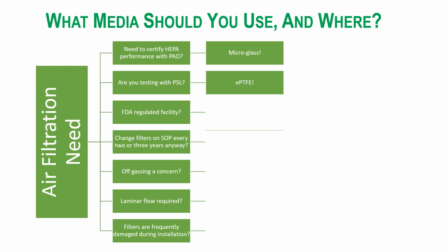You can't just switch from PAO to PSL. You have to buy a different particle counter. You have to buy a different nozzle. It's a completely different monster to adopt. So if you're an FDA regulated or Health Canada regulated facility, you probably want to stay on what you're using already, or you want to be ready to explain why you switch to a PTFE media, for example.